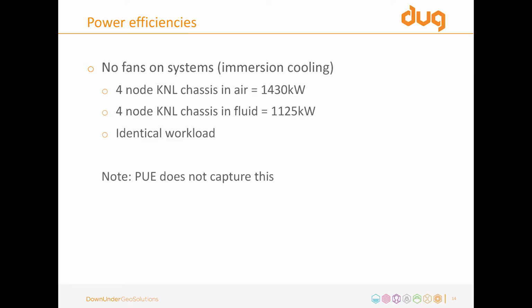We have no fans on the compute nodes. You've all heard me bang on about this before, I guess. This is a real impact. You take the fans off, because you're immersion cooling, you drop the chassis from 1430 kilowatts down to 1125. Identical workload. Exactly the same compute throughput, and you've dropped this much energy just by removing the fans. Guess what? PUE doesn't capture that. That's a saving we get that doesn't impact our PUE. So what's that, 22% or something? Quite significant. So we've got transformation, better efficiency PSUs, and the 22% due to taking your fans off.